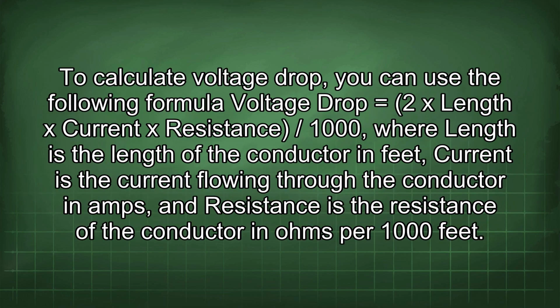To calculate voltage drop, you can use the following formula: voltage drop equals 2 x length x current x resistance / 1000, where length is the length of the conductor in feet, current is the current flowing through the conductor in amps, and resistance is the resistance of the conductor in ohms per 1000 feet.